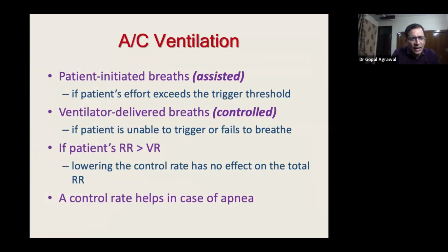Suppose the baby is breathing at a lower rate or is apneic, the ventilator will go into a controlled mode where it will deliver its set backup rate. So there are two modes here, assisted and controlled. If the baby's breathing rate is equal to or higher than the set machine rate, it will assist all the breaths. Controlled mode is when the baby's breathing rate is less than the ventilator's backup rate, where it will control all the breaths. It will be delivering the set fixed rate of 30 breaths.